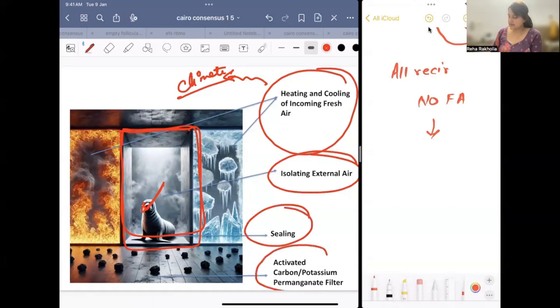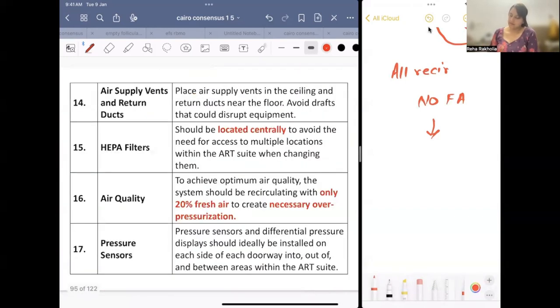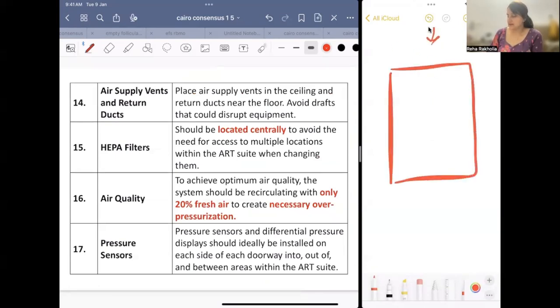And then activated. See this picture, it contains charcoal. Okay, activated carbon and potassium permanganate filter. Now 14th point is air supply vents. What should be there? The incoming air should come from above and the outgoing air outlet should be near the floor. Okay, HEPA filter. HEPA filter should be located centrally.